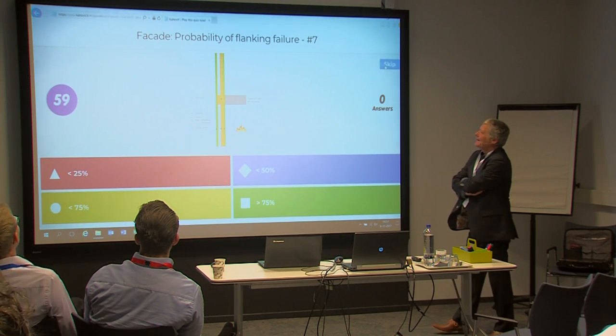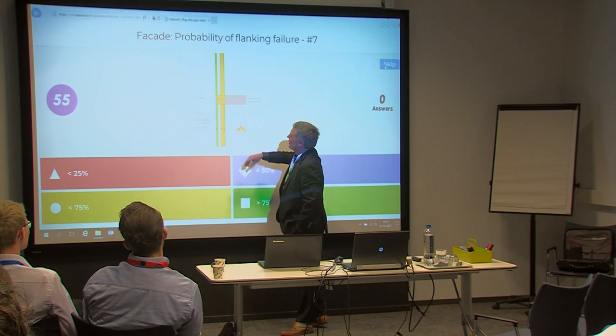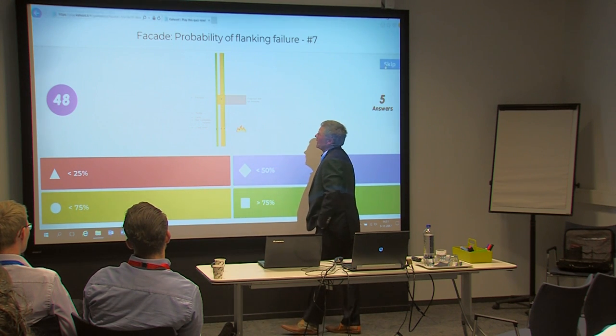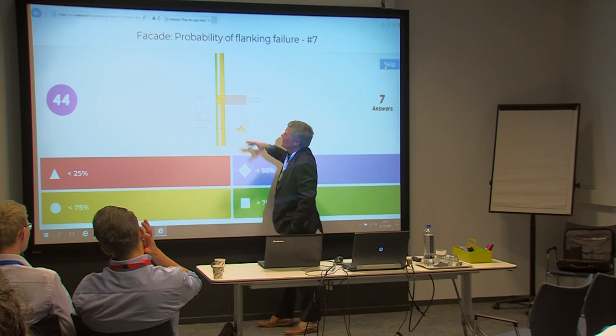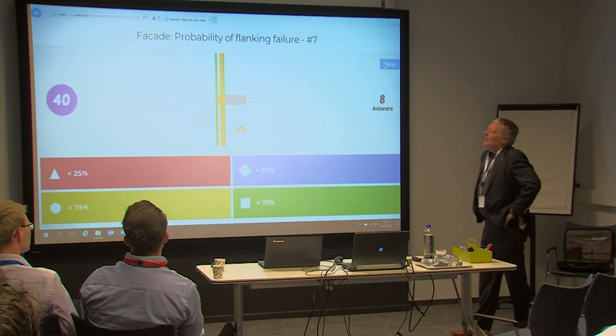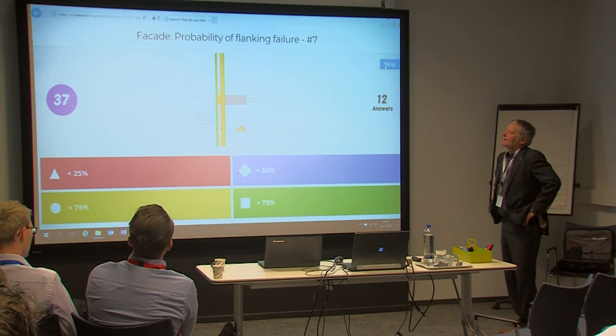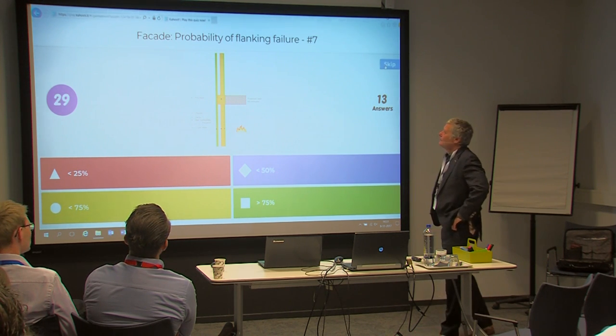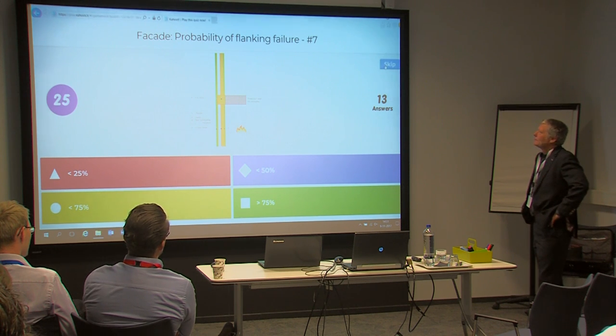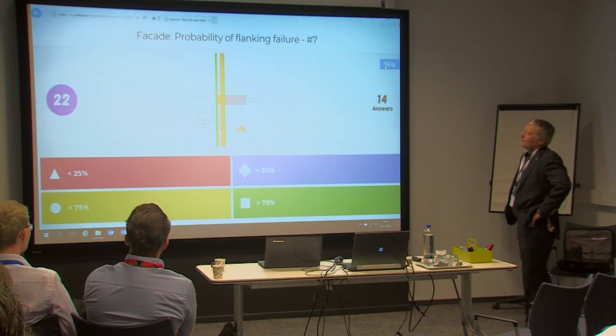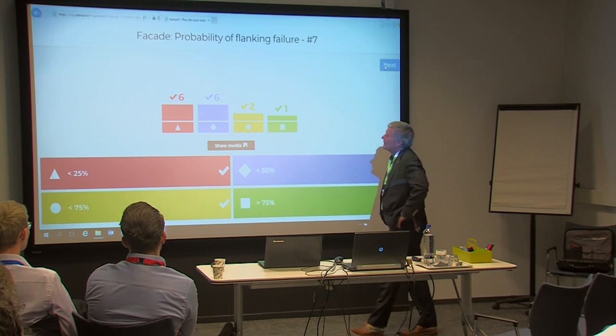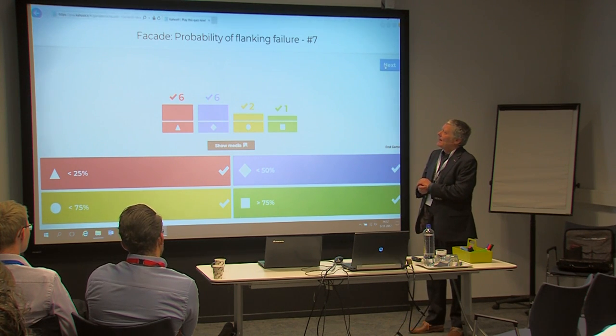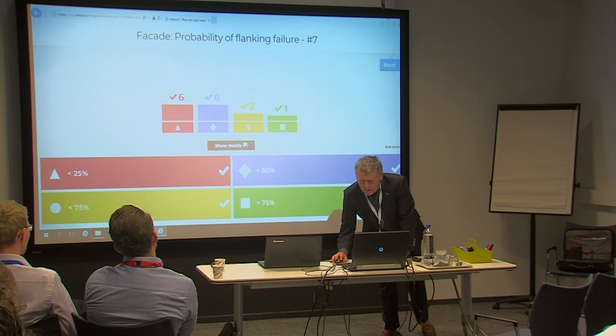The seventh facade detail: also a cavity facade with non-combustible material, but the firewall stops at the facade and there is a fire block that blocks both conduction and convection. How effective is that fire block? Results show some efficiency is recognized, but there is still quite large spread in answers — the group is not fully convinced about the effectiveness.